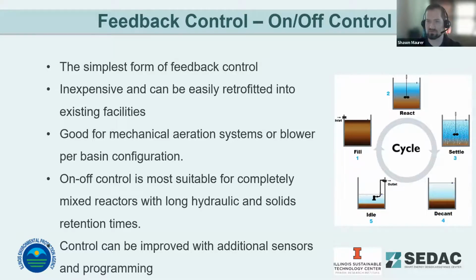But it's a little more difficult to accurately control if you've got a single blower feeding multiple basins, multiple different systems. A lot of plants with activated sludge will see a blower that's serving your activated sludge basins and also an aerobic digester, possibly. And you can't really do on-off control with an automated system with those. You need a little bit more advanced control than that. Ideally, you see this control for fully mixed reactors with long hydraulic and solids retention times. And you can improve this control with some additional sensors and programming.